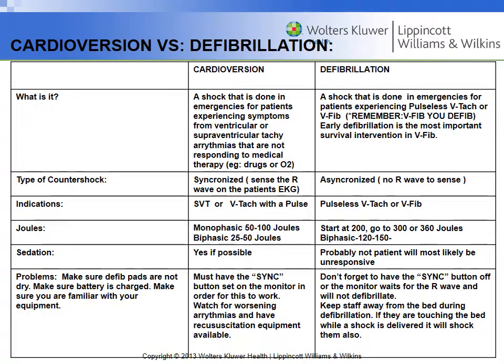In both monitors, make sure the defibrillator pads are not dry. When you take them out of the package, they should feel moist and sticky. If they're not, they're not going to work. Also, make sure your battery is charged. Monitors will not work if the battery is not charged. And make sure, this is most important, that you're familiar with your equipment.